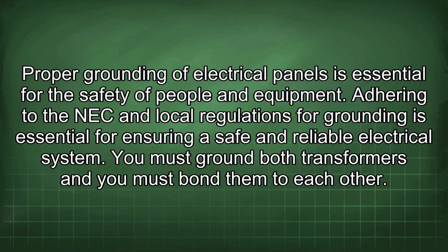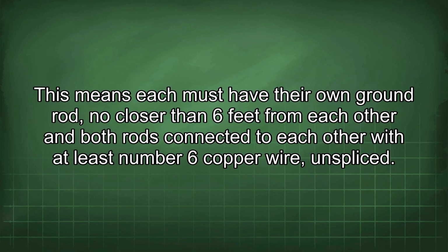You must ground both transformers and you must bond them to each other. This means each must have their own ground rod, no closer than 6 feet from each other, and both rods connected to each other with at least number 6 copper wire, unspliced.